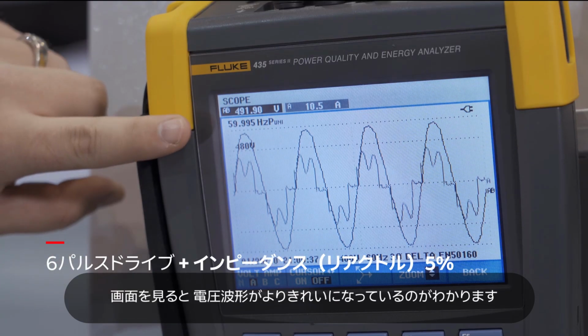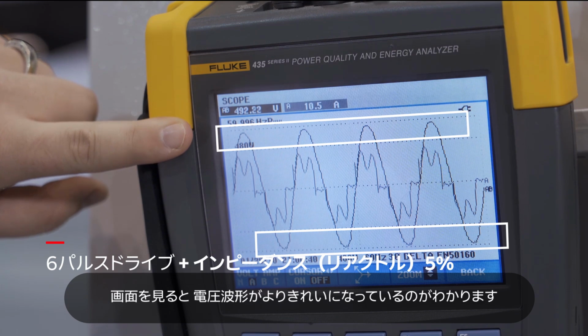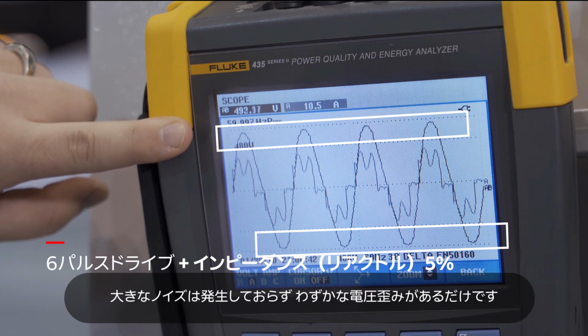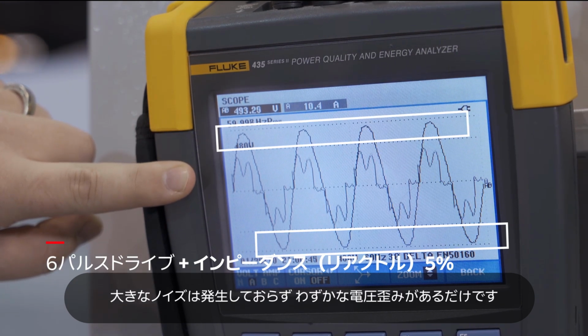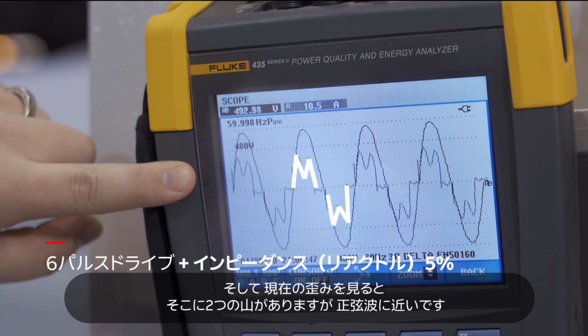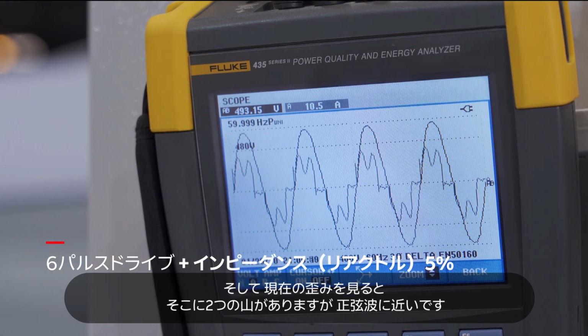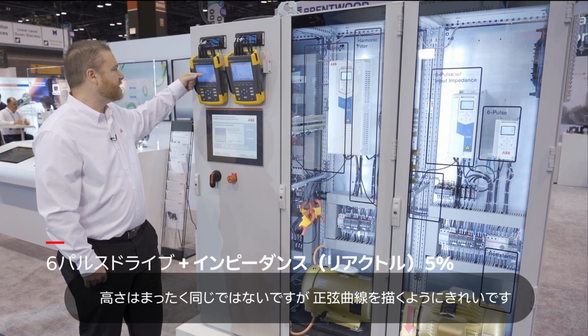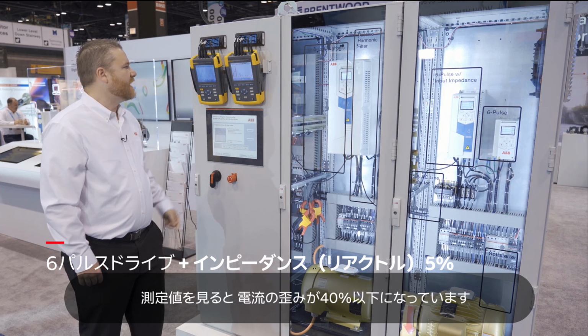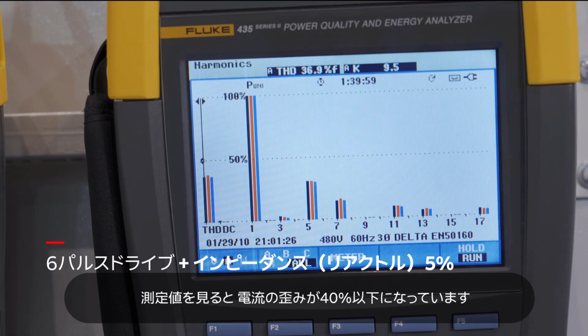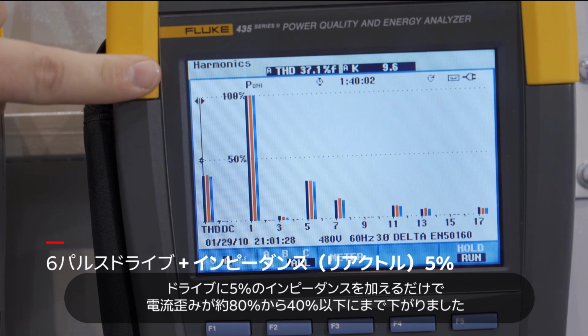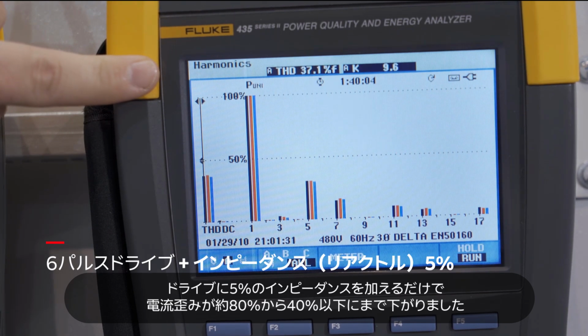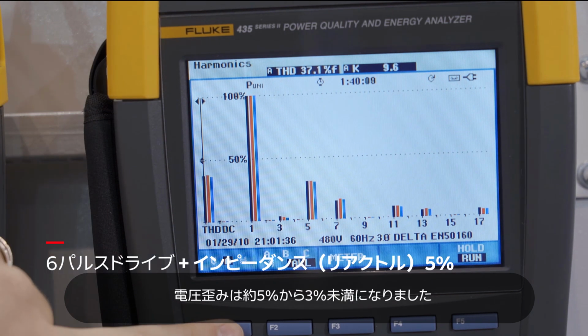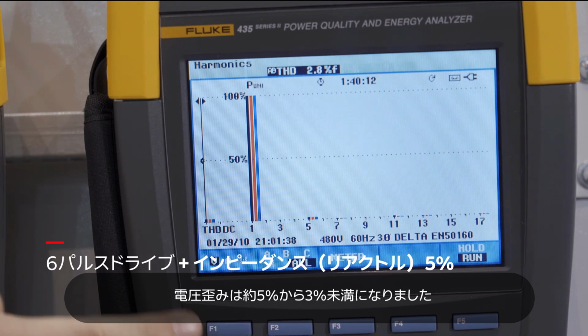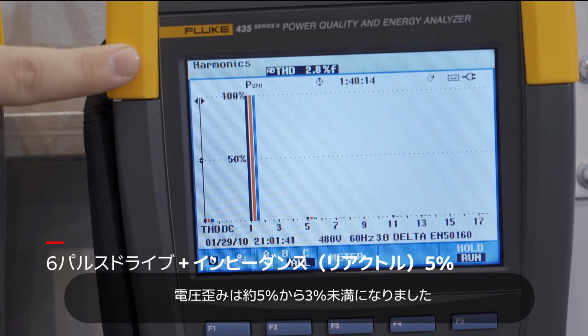And going back to the scope images again, you can see your voltage waveform is much cleaner. There's no more of that significant flat topping, just a small amount of voltage distortion. And then when you look over at the current distortion, you've got your 2 bunny ears there, but it's much more sinusoidal. They're not nearly as tall, and it follows that sinusoidal path much cleaner. Now I come over here and look at my measurement, and I'm under 40% current distortion. So just by adding that 5% impedance in the drive, I went from almost 80% down to less than 40%. So I cut the current distortion in half, and my voltage distortion went from almost 5 to less than 3% voltage distortion, so much better.